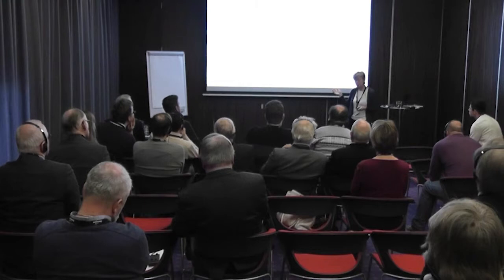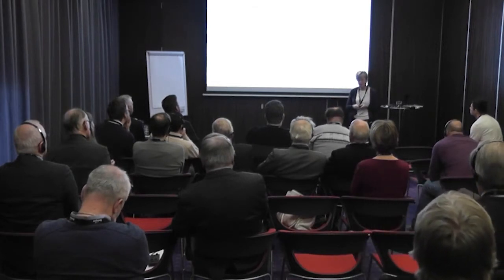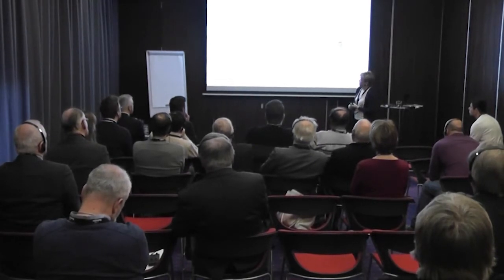So, but I think it was interesting to have this as a background to explain for the customers that they could not expect the standard values, but they could expect something better than this. So we were working towards that. And here they also explain that it's the ventilation that is the main challenge and the main reason for the high energy use. So the ventilation here at this project is a bit above 1 million cubic meter per hour that is treated in this building.